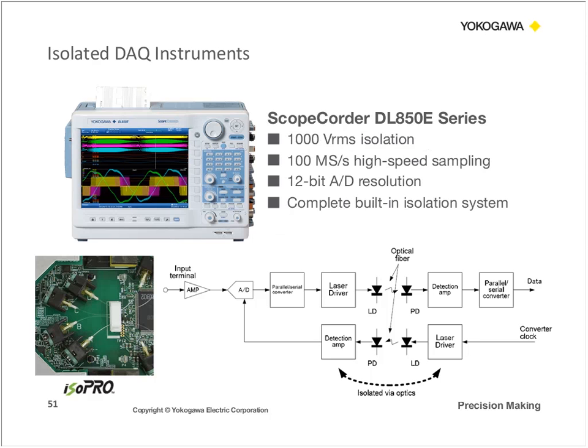So I just want to quickly cap off with one of the ways Yokogawa implements our technology in terms of isolation. What I have here is our modular scope corder DL850E series. It's a modular system that implements a combination of optical and digital isolation. And what this allows you to do is you can have up to 16 channels of very high speed, 100 megasamples per second sampling speed per channel. And it gives you very good resolution as well. So you have not only 12-bit A to D resolution, but even in certain cases up to 16-bit resolution. And to put that into perspective, 16-bit resolution is approximately 5 to 6 significant digits. So this is what you would find on very highly accurate systems, power analyzers as well.